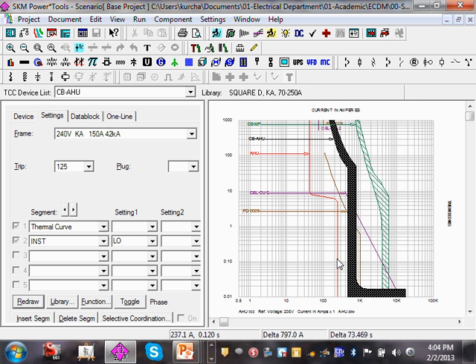For the low voltage, it goes the opposite. We start with the full load. That's what we care about. I want to carry the full load, and then the voltage drop, and then the last one is short circuit in the low voltage system. I'm sorry. Any comments, guys? Any questions, besides the conductor rating system? You size the system contingency first and load second.